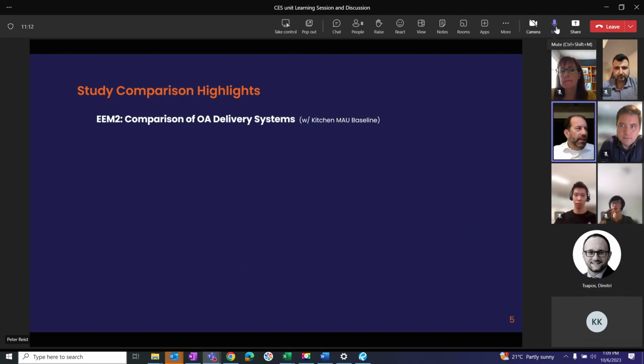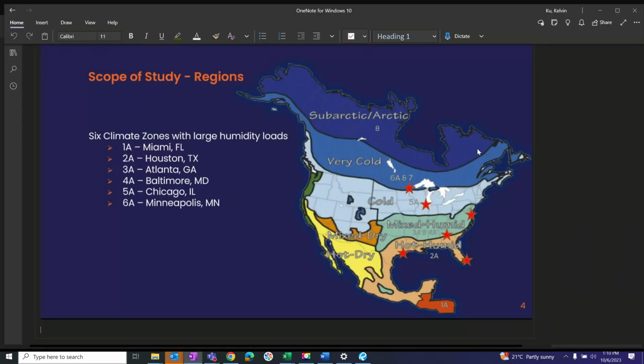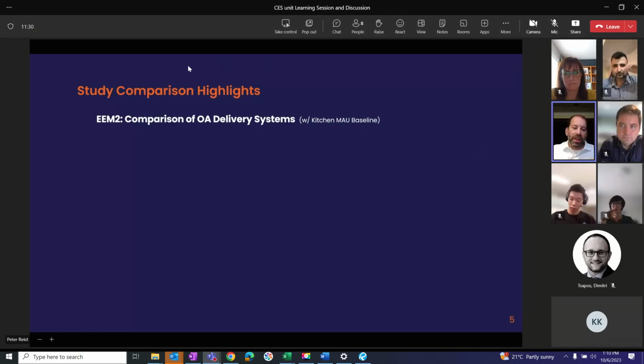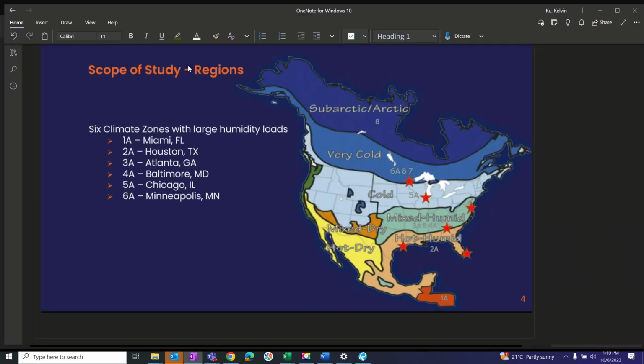This is kind of mainstream these days, but what they essentially concluded is you want 90% of your exhaust made up by local makeup air units, with 10% transferred in from the sales floor. That's what they set as the baseline, the best in class. There's a whole study in this report about what that looks like and the different energy benefits.